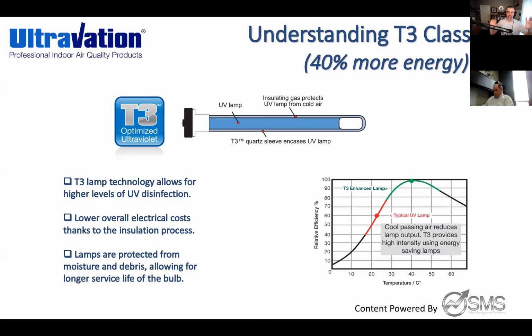As long as you're using a UVC class lamp and it's a 1 year life cycle bulb, it could have a 2 year warranty. But if it's not T3, that's a 9,000 hour bulb, meaning it's a 1 year life—I should be swapping them, maintaining them, doing preventive maintenance once a year.